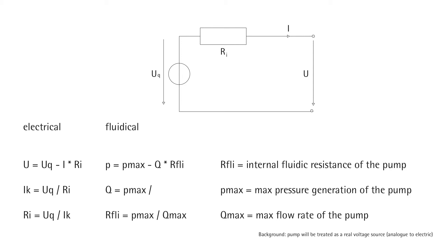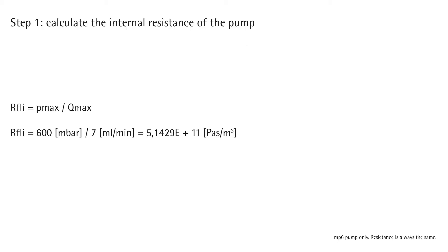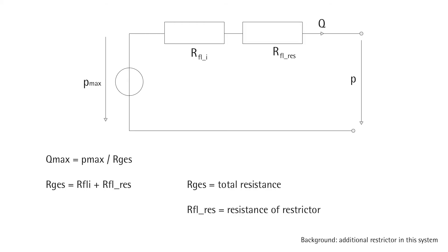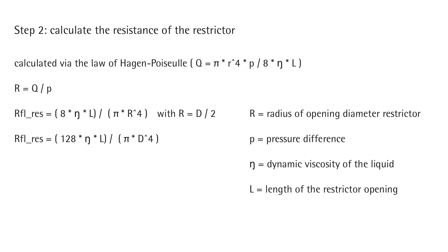Calculating a suitable restrictor can be done by treating the pump as an electrical circuit, calculating the internal fluidic resistance of the pump, adding the restrictor as a resistor, and applying the law of Hagen-Poiseuille to determine this resistance. The maximum flow rate is then dependent on the total resistance of the system.